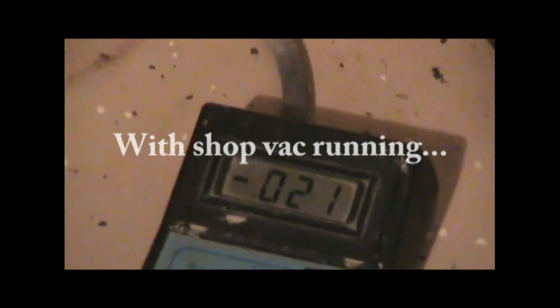We're looking for the difference between the pressure under the slab and the pressure above the slab. We normally have a positive soil pressure — when the house is negative relative to that, it pulls radon in. This reading shows a positive four thousandths of an inch underneath the slab. We like to see a change of at least five thousandths; ten is pretty good. This one went from a positive four to a negative twenty-one, so that's great — and that's with very small airflow from the vacuum and the hole under the bathtub still not filled. So it should work great.